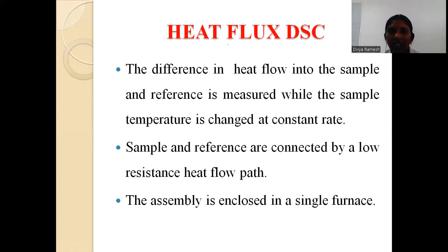Next one is your heat flux DSC. In the previous case the power will be measured. Here the heat flow into the sample and reference will be measured, and those changes can be kept constant.